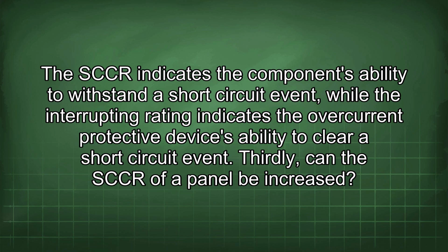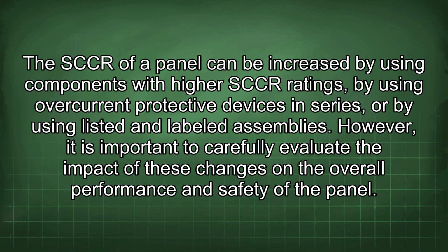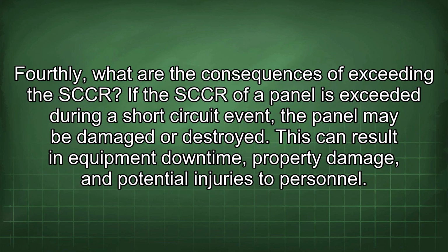Thirdly, can the SCCR of a panel be increased? The SCCR of a panel can be increased by using components with higher SCCR ratings, by using overcurrent protective devices in series, or by using listed and labeled assemblies. However, it is important to carefully evaluate the impact of these changes on the overall performance and safety of the panel. Fourthly, what are the consequences of exceeding the SCCR?